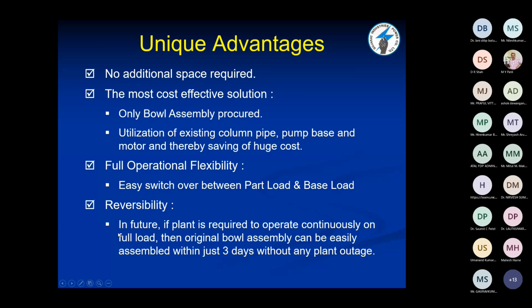Okay, this is the reversibility. In future, if the plant is required to operate continuously at full load, then the original bowl assembly can easily be assembled within just 3 days without any plant outage. If the scenario changes and the plant is to be operated at full load, we can easily remove the new bowl assembly, replace it with the old bowl assembly, and use the original pump.